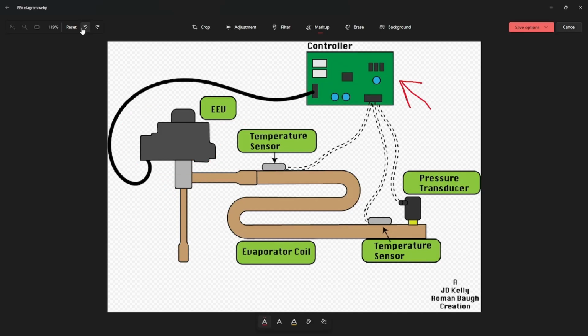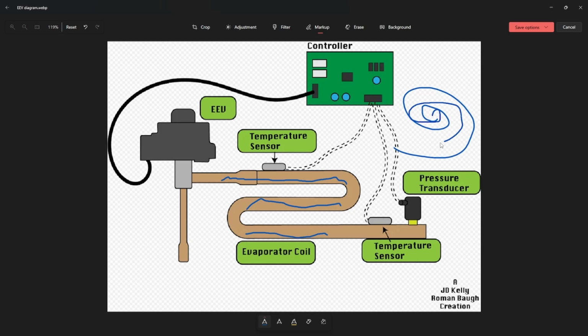For example, if you have an inverter-driven compressor, inverter-driven compressors can ramp their compressor RPMs down extremely low, and that reduces the velocity of the refrigerant as it's traveling through our coils. Well, when you slow down the velocity of the refrigerant, you can leave something behind. What you leave behind is oil. So you'll have oil coating the bottom of the coil, just sitting in here. Well, that's a problem. Because remember, our compressor needs to have oil circulating through it to keep all of the scroll plates properly lubricated, so that way you don't get metal on metal contact.